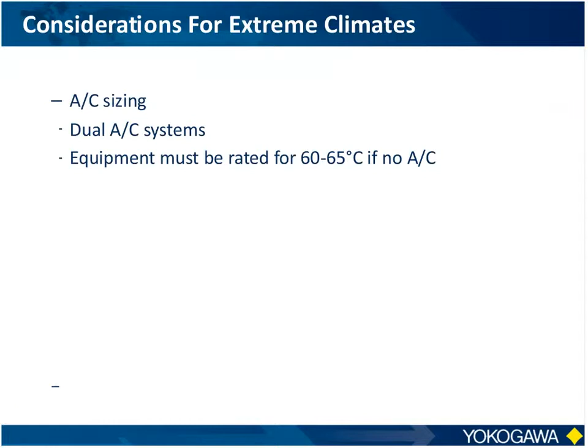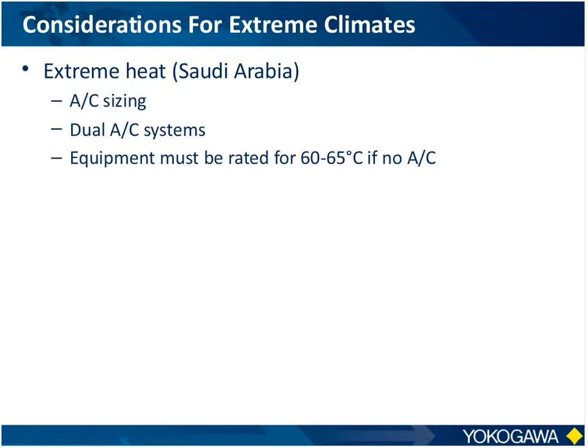One of the things I mentioned was air conditioner systems, especially in areas like Saudi Arabia or similar regions where you can get very big requirements on the air conditioning systems. Aramco, for example, typically requires backup air conditioners. If you want to avoid that cost, they say your equipment installed inside needs to be suitable for use up to 65 degrees C.